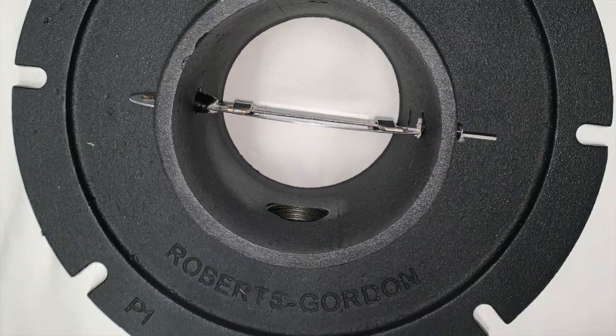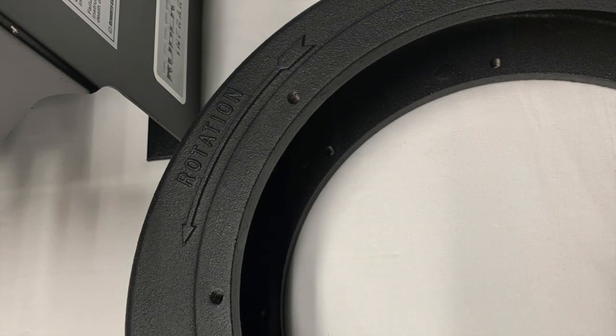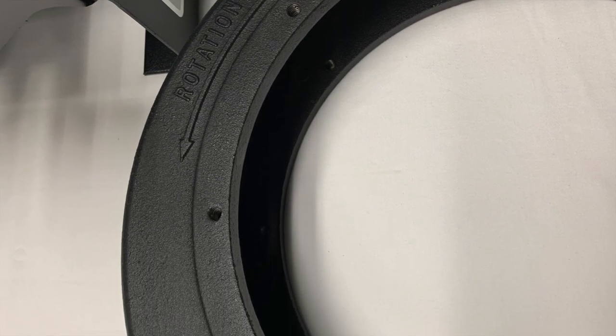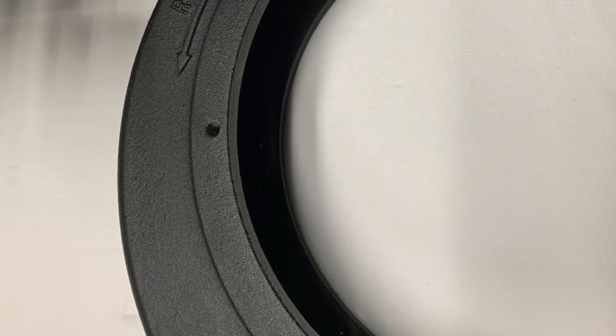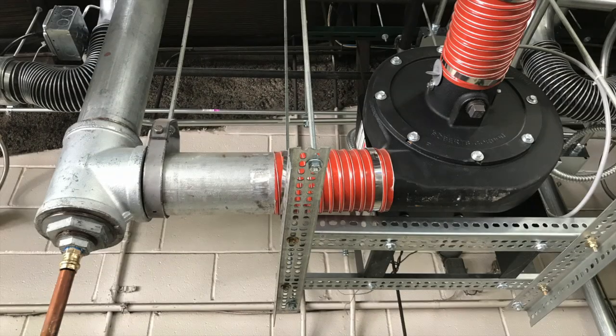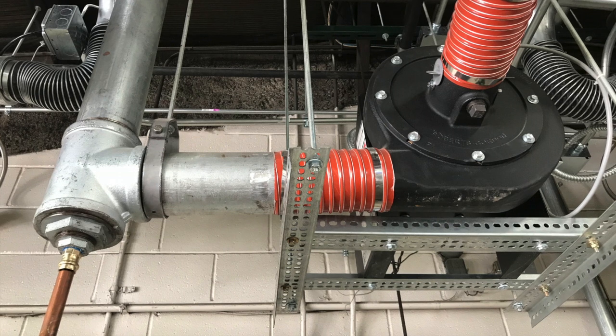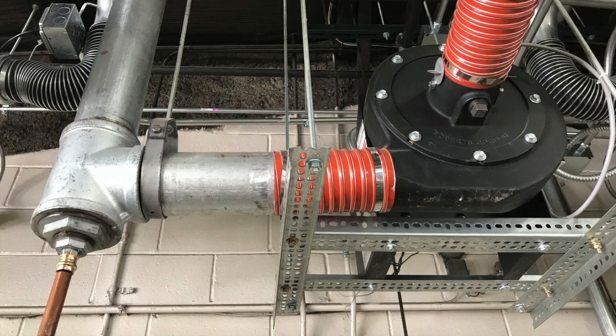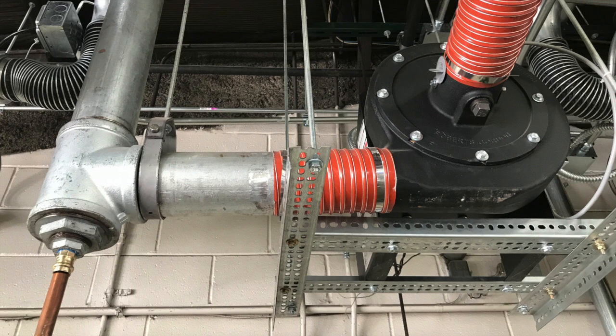The scroll discharge is bottom right or bottom left only. You can install 1 bolt on the bottom through the gasket. Then place the inlet plate down over the bolt and put the remaining bolts in and torque approximately 40 foot-pounds.